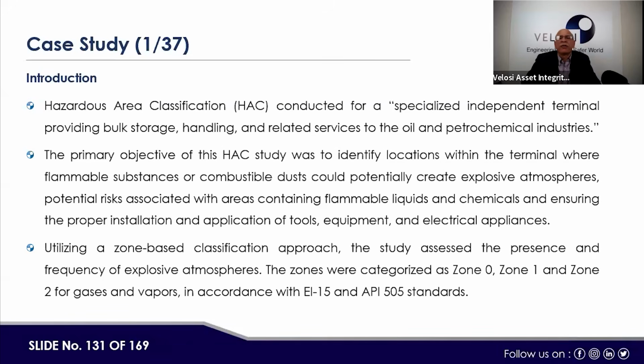So, hazard area classification was conducted for a specialized independent terminal providing bulk storage, handling, and related services to oil and petrochemical industries. The primary objective of the HAC study was to identify locations within the terminal where flammable substances or combustible dust could potentially create explosive atmospheres, the potential risk associated with areas containing flammable liquids and chemicals, and ensuring the proper installation and application of tools, equipment, and electrical appliances. Utilizing a zone-based classification approach, the study assessed the presence and frequency of explosive atmosphere. The zones were categorized as zone 0, 1, and zone 2 for gases and vapors in accordance with EI-15 and API 505 standards.